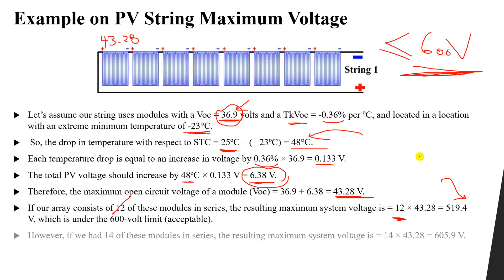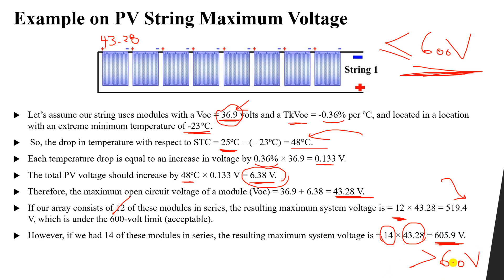However, if we assume 14 modules in series, the system voltage would be 14 × 43.28V = 605.9V, which is greater than the maximum system voltage of 600V. Therefore, 14 modules in series is rejected because the 600V limit is exceeded. The maximum number of modules in series is 12.